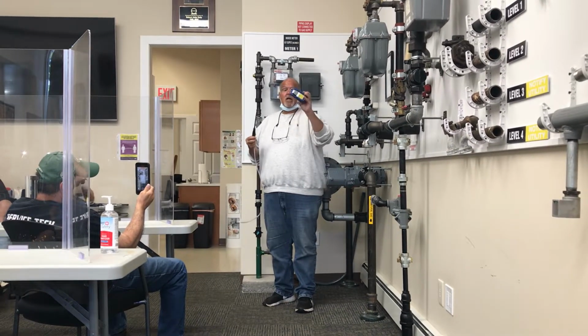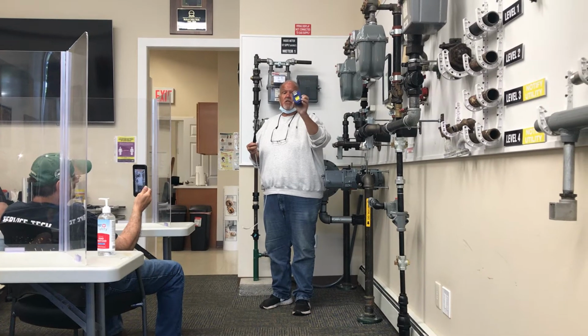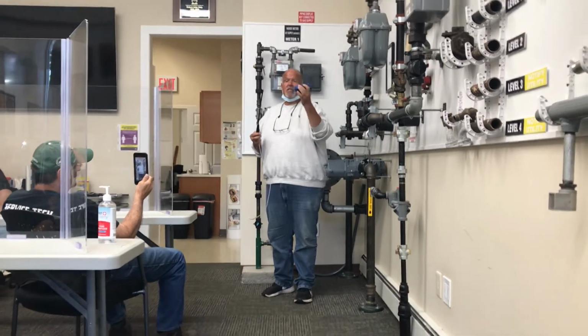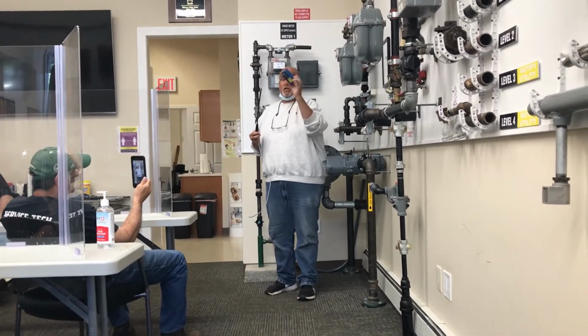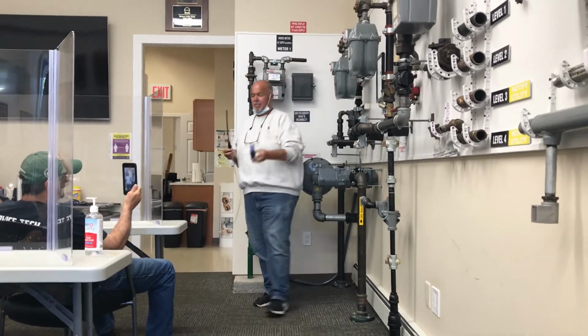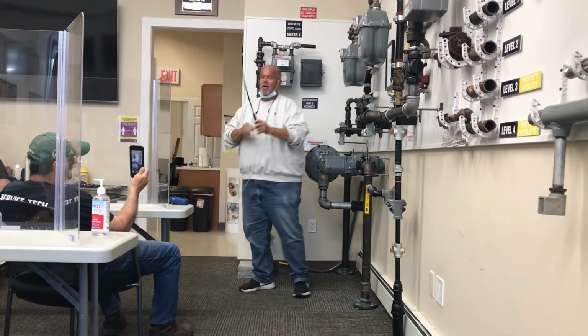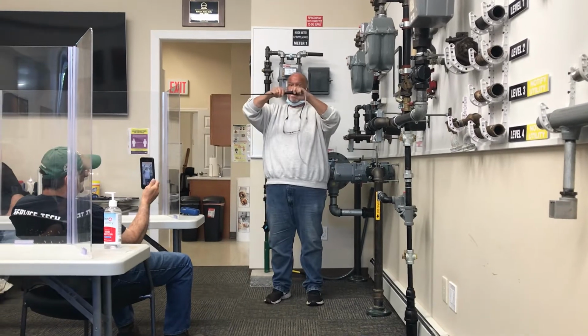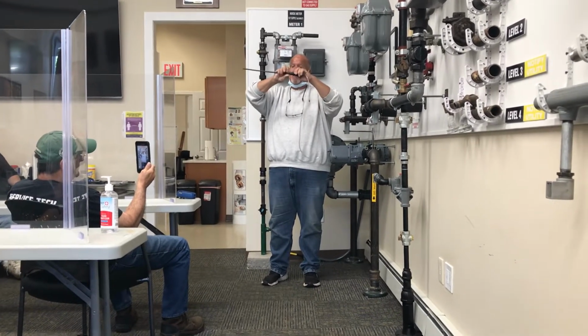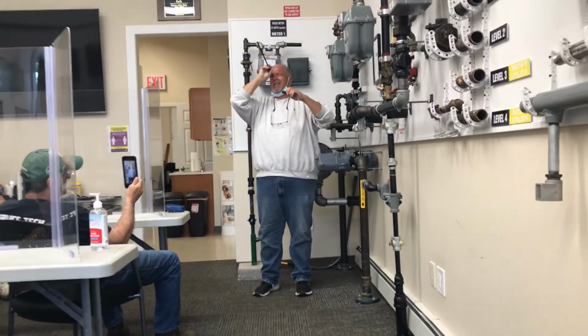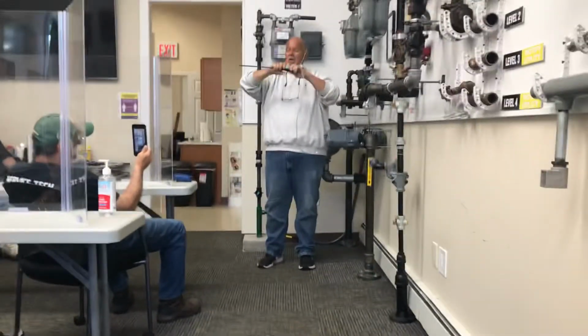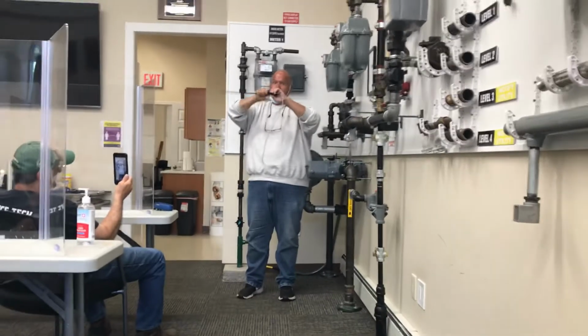First thing you do, check all 6 sides of the combustible gas indicator. Make sure it's not dented, damaged, cracked, or broken. Everything looks okay. Terrific. Next, unscrew the probe from the probe handle. Hold it up to the light. If you see the light, you've confirmed that the probe is not clogged. Reconnect the probe to the probe handle.